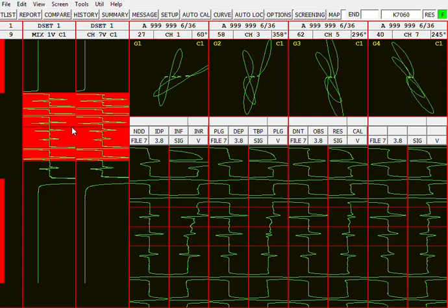So in a heat exchanger where there's a bunch of tube supports or structures that are supporting your tube, they can easily mask indications of flaws. So you'll make a mix to basically erase the non-relevant signature and only display the flaw data.